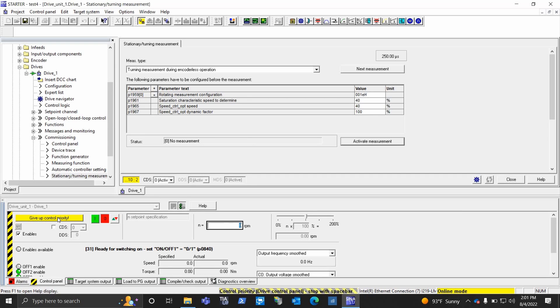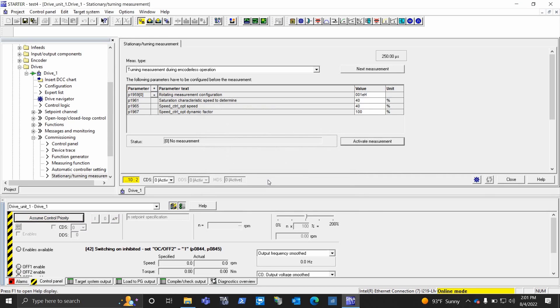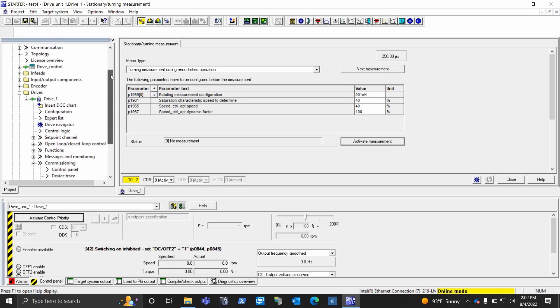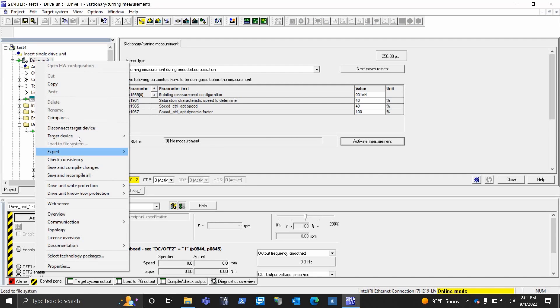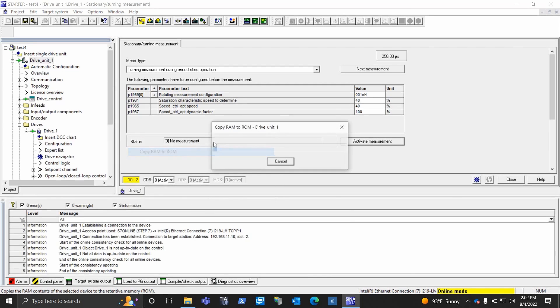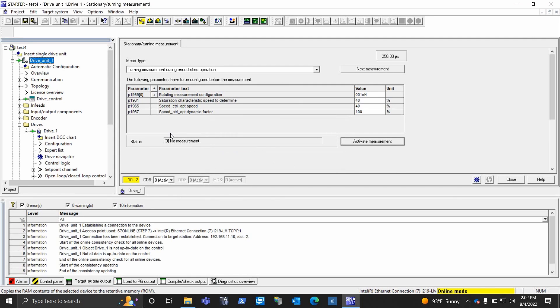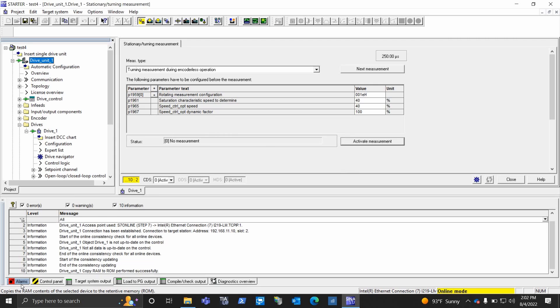Now I'm going to go ahead and give up control. It gives control back to the PLC, and you can only do this if the PLC is not actually running the motor. It won't switch control otherwise. So now I like everything, so I'm going to go up here to target device, say RAM to ROM. Now it's going to permanently write everything into the EEPROM of the drive. It actually saves it on that card as well. Alrighty, so now it tells me it'll make a backup copy on the memory card next power cycle. So that's just typical. You don't actually have to cycle power right now, but it will back it up the next time it's power cycled for you.